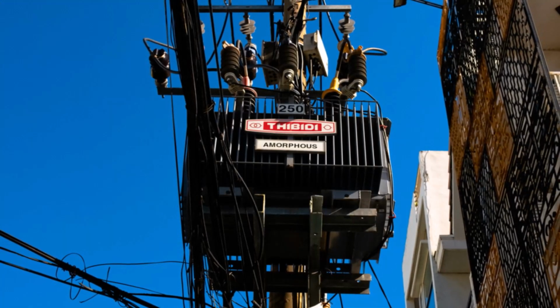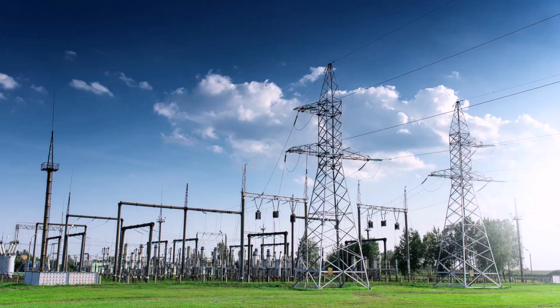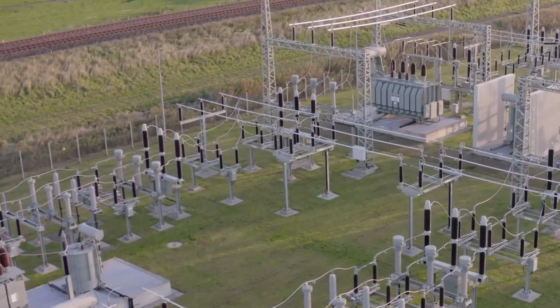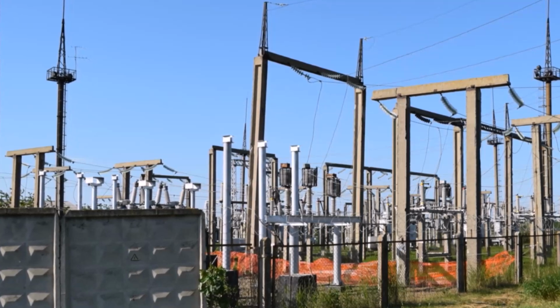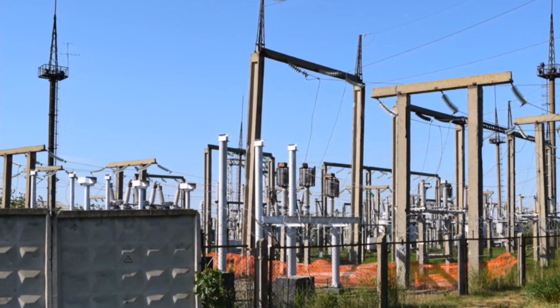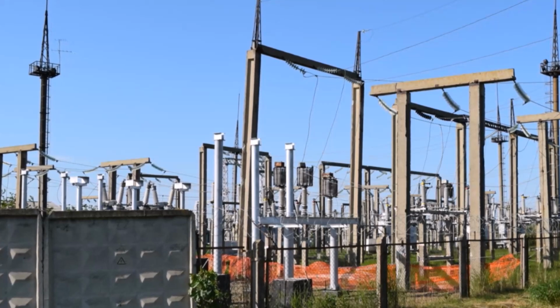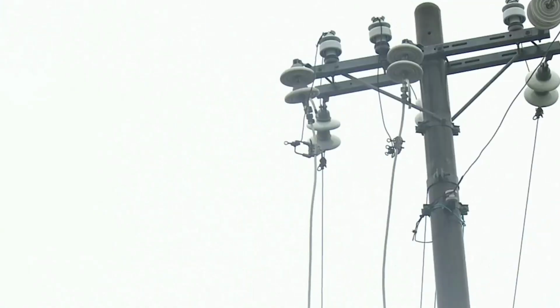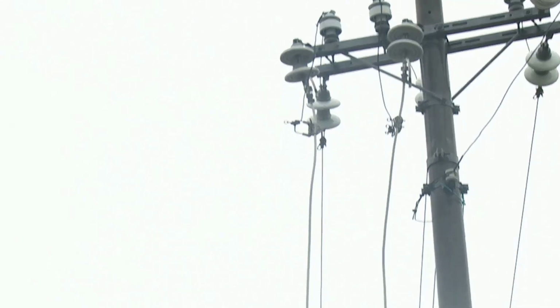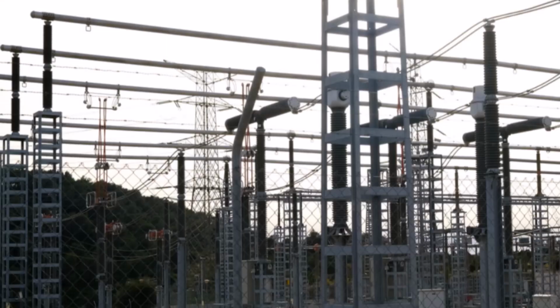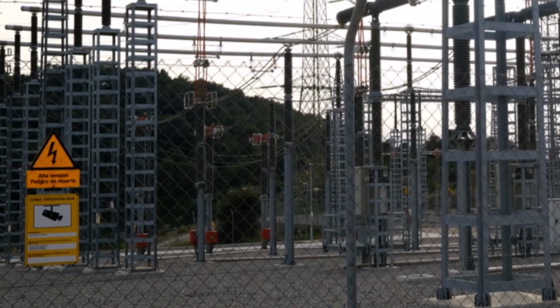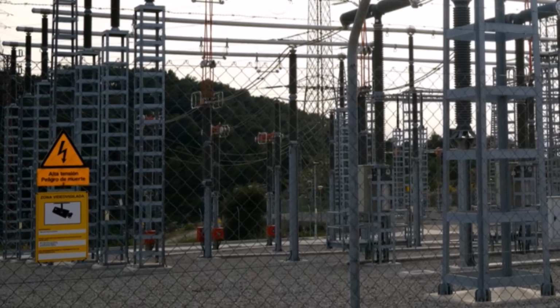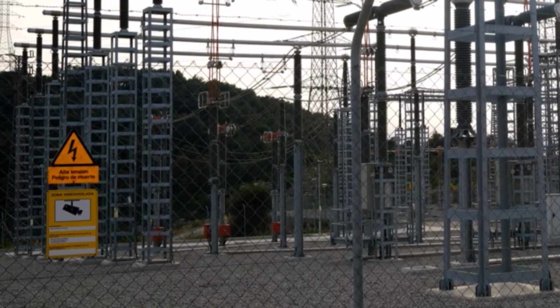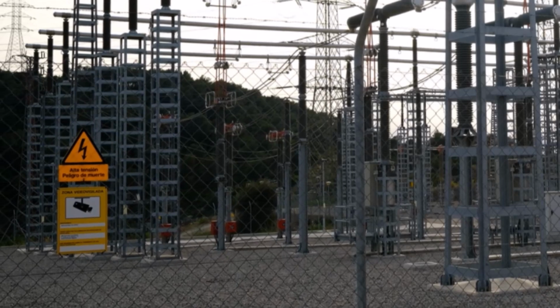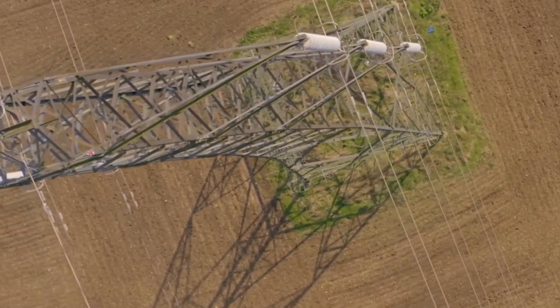Transformers are another place where Y connections are essential. A transformer is a device that changes the voltage of electricity up or down, and its internal coils, or windings, can be connected in several ways. The Y connection is a very popular choice for these windings. Sometimes only the secondary low-voltage side of a transformer is connected in a Y configuration to provide a neutral point for local distribution. In other cases, such as in large power substations, both the primary, high voltage, and secondary windings might be connected in a Y, creating what is known as a Y-Y transformer. This is common in high voltage transmission systems.